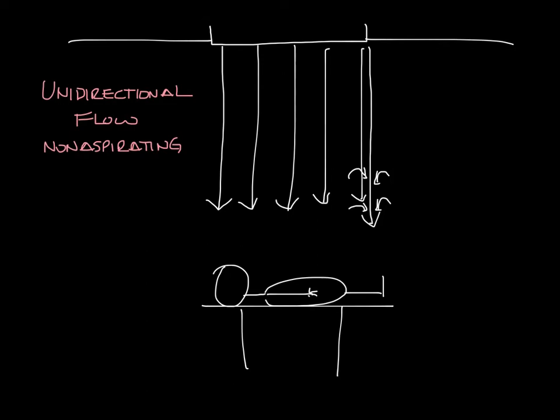In super simple terms, it's a diffuser where the airflow is moving in one direction and it's not drawing room air and particles into the airflow stream. You also don't want the airflow velocity to be so high that it's blowing particles into the surgery site on the patient. You basically want ultra-clean slow moving air over the patient.